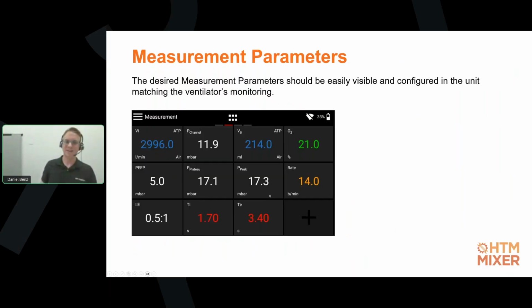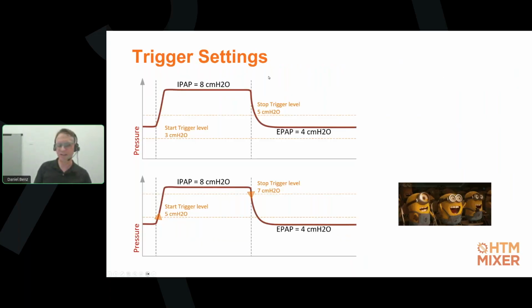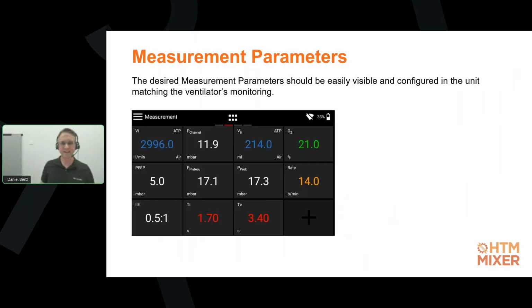So long story short, particularly in BiPAP applications, you will have to understand your trigger settings and set them accordingly. So that was it about the trigger settings. The last thing on challenge number 2 here, on the setting side, is the settings of the values you're looking at.